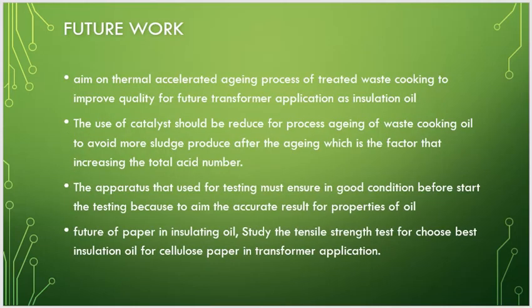For future work, aim on the thermal accelerated aging process to improve quality for future transformer applications. The use of catalyst should be reduced to avoid more sludge produced after the aging, and the apparatus must be ensured in good condition before starting the testing. And for future work on insulating oil with paper, study the tensile strength to choose the best insulating oil for cellulose paper in transformer applications. That's all for me.